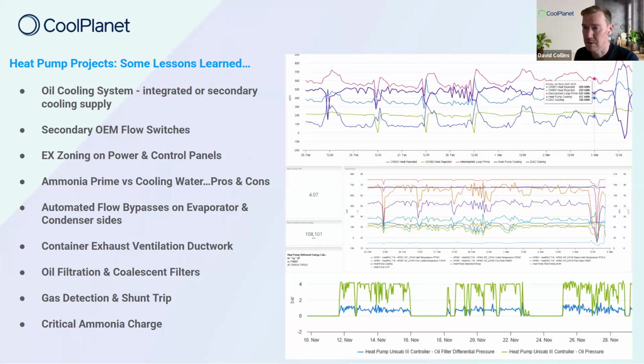There are a couple of things we found out post-installation that resulted in retrofits with the OEMs, but you need to make sure they're addressed going in. I've touched on the benefits of ammonia prime versus cooling water—if you can capture the prime directly from ammonia, it's probably a higher grade of heat, but it does have complexities, so you need to know what you're doing. Working with designers and contractors who have experience with refrigerant pipework is key, as is having an automated bypass around the heat pump, because when demand dips you want to recirculate that already preheated water back towards a buffer vessel. There's no need to send it into a heat pump if the demand isn't there.